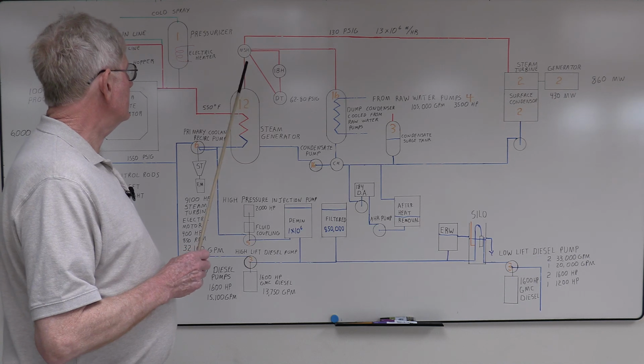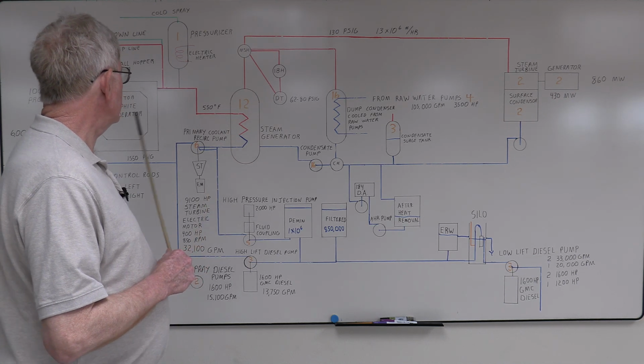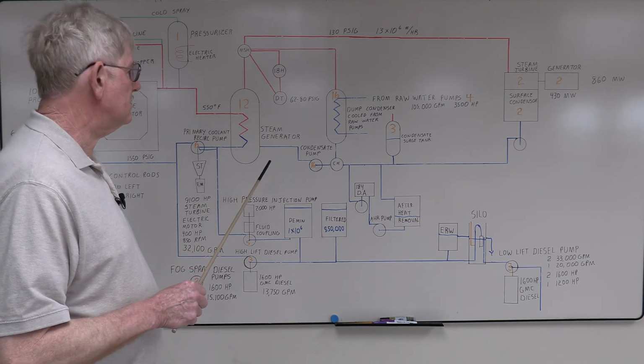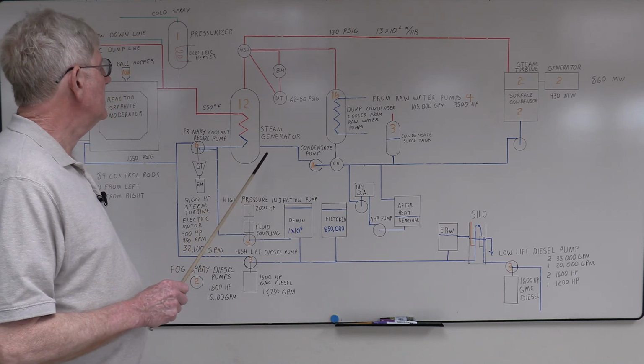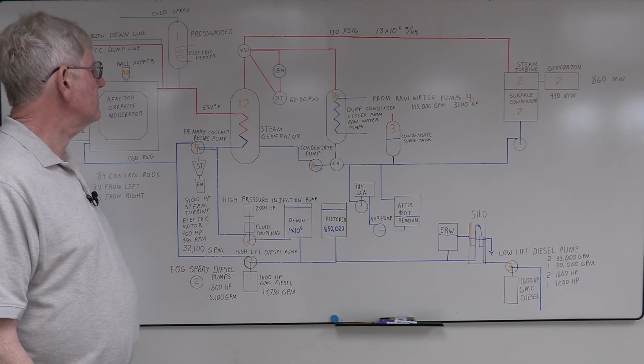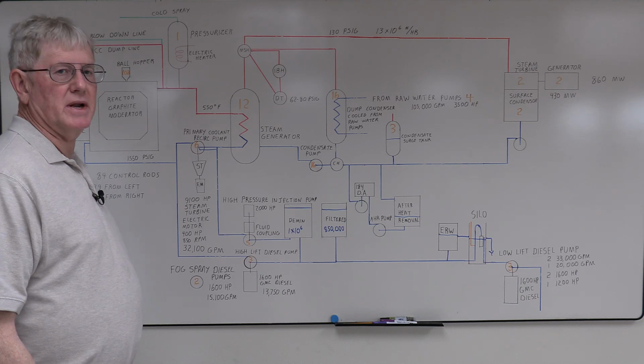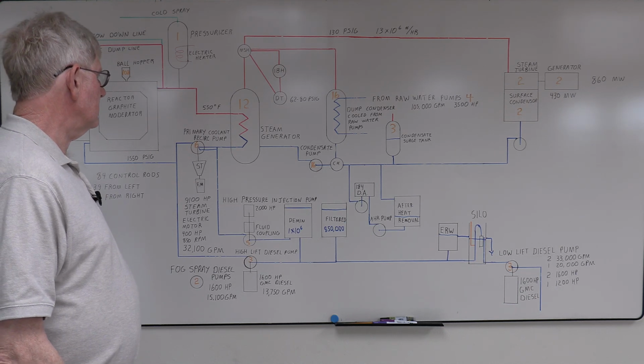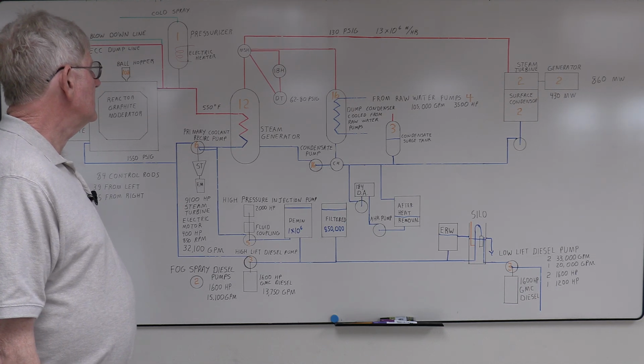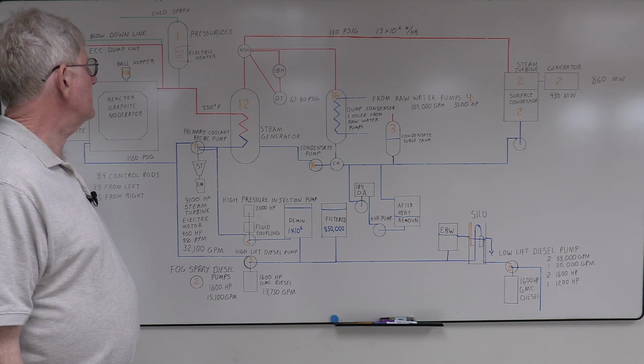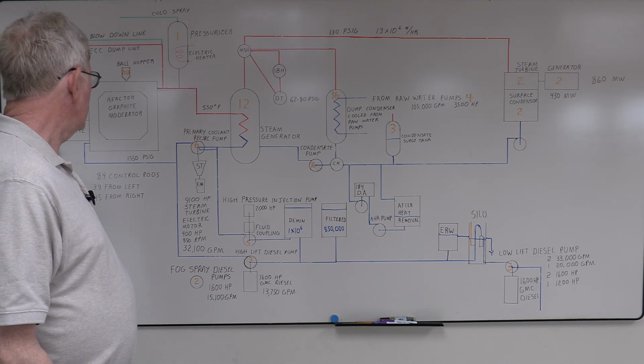If the plant scrammed, it had what they called a thermal flywheel. There's enough residual heat in the plant to provide steam for about a half hour. The boilers were kept in hot standby, so you could ramp them up in a half hour and grab the steam load, keep your turbine generator running for the plant power.